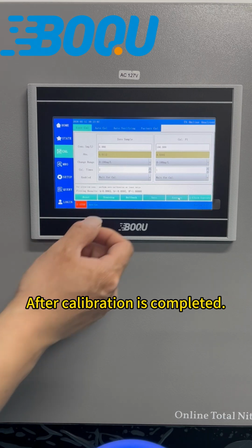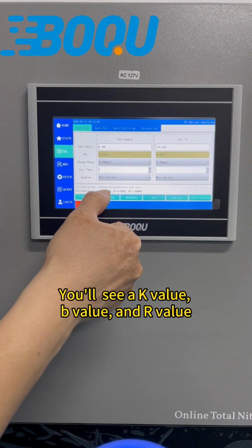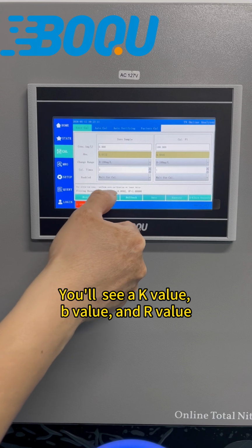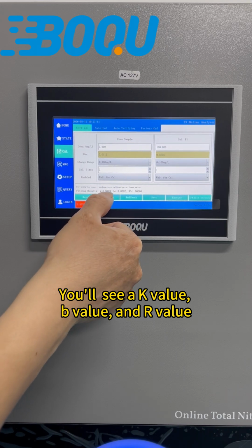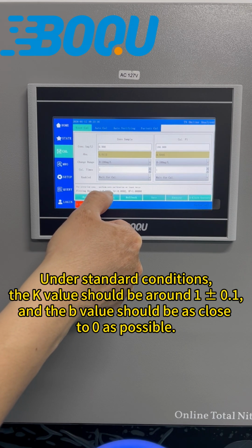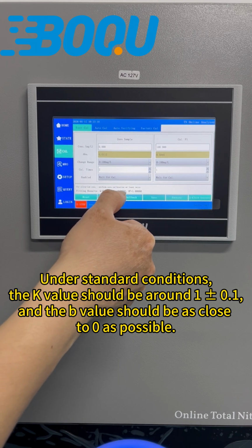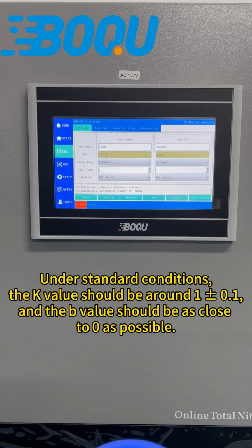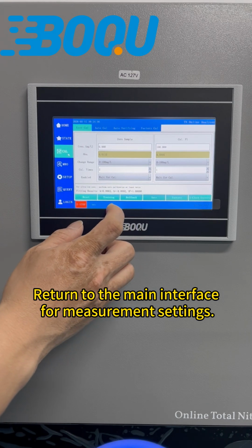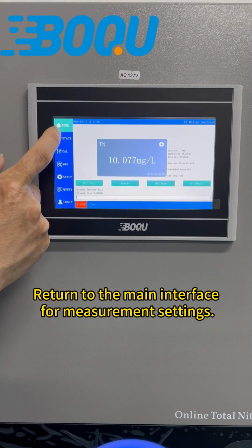After calibration is completed, you will see the K value, B value, and R value. Under standard conditions, the K value should be around 1 plus or minus 0.1, and the B value should be as close to 0 as possible. Return to the main interface for measurement settings.